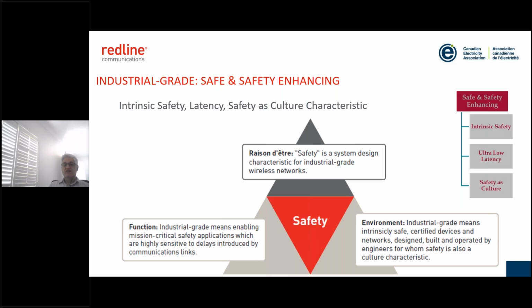Any device or equipment you deploy in that environment must be inherently safe, so that intrinsic safety certified devices, like C1, D2 certified devices, are important when deploying these networks in this kind of environment from a safety perspective. The last thing we would want is for a wireless radio to become an explosion hazard in such an environment.